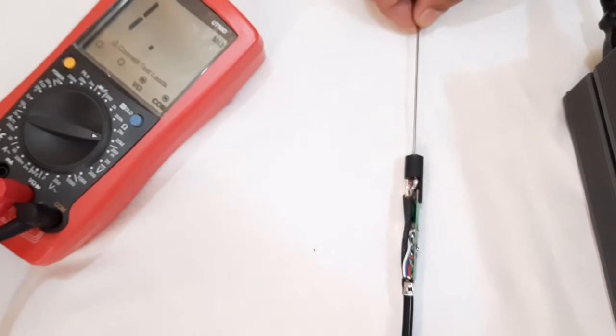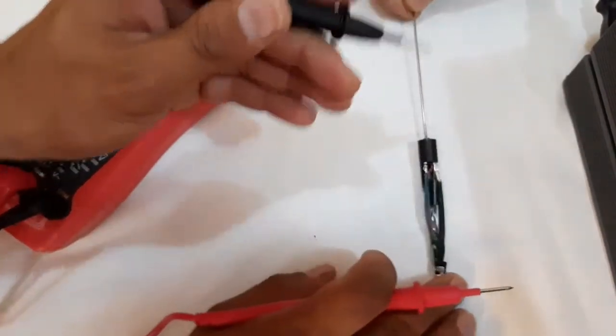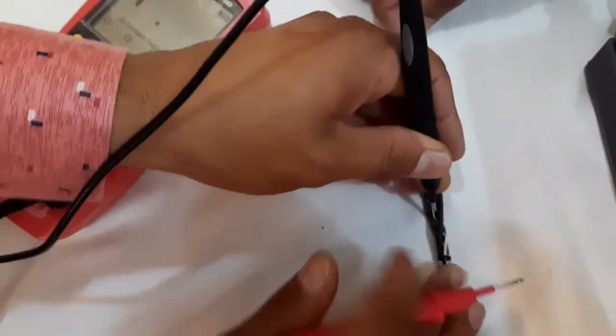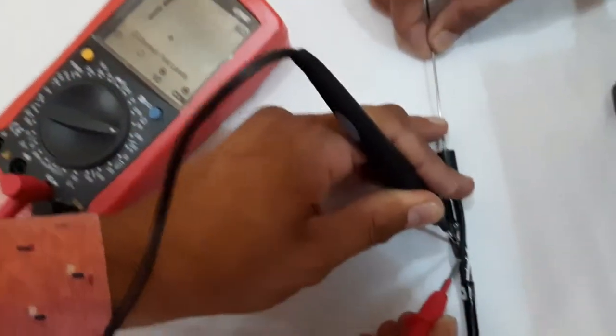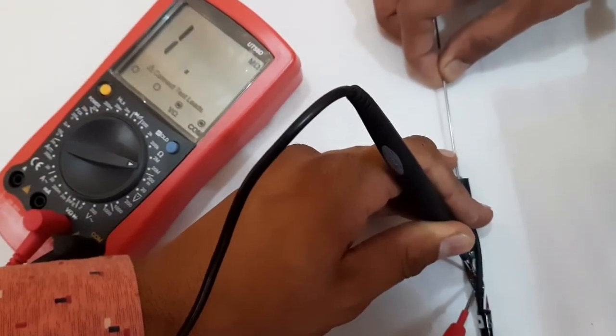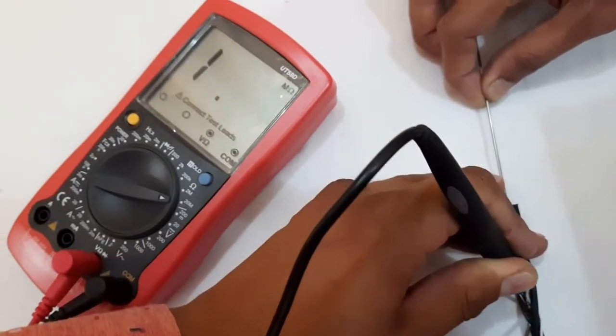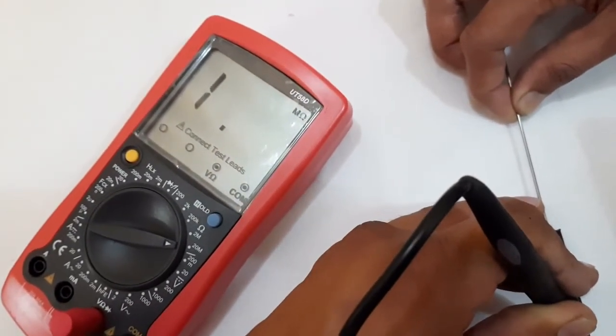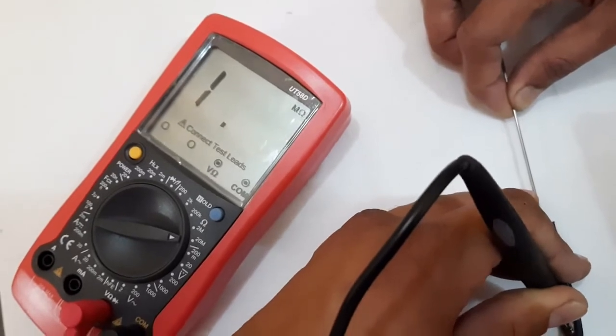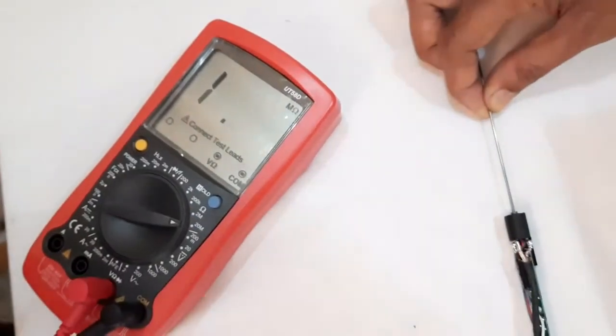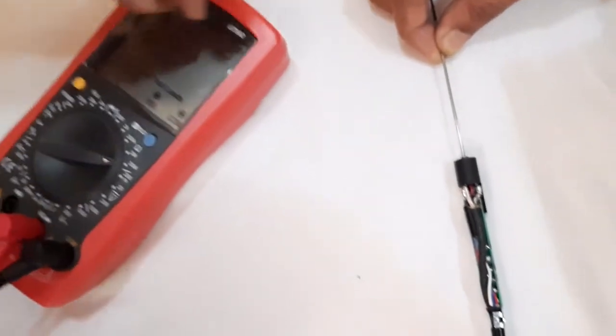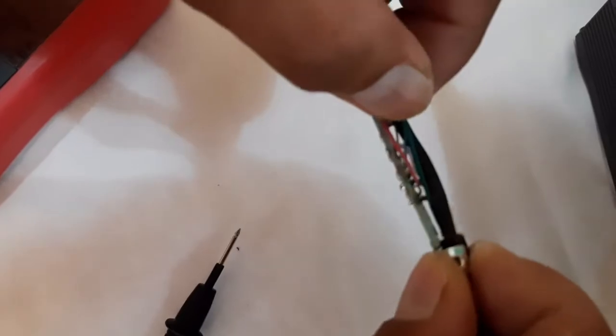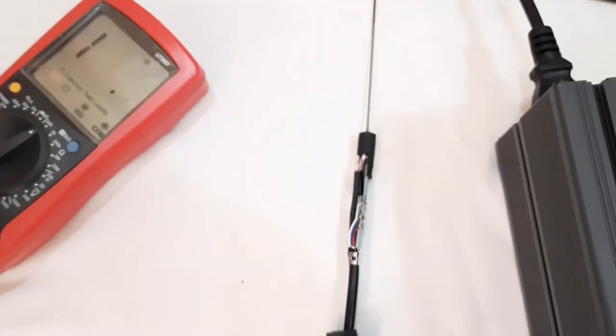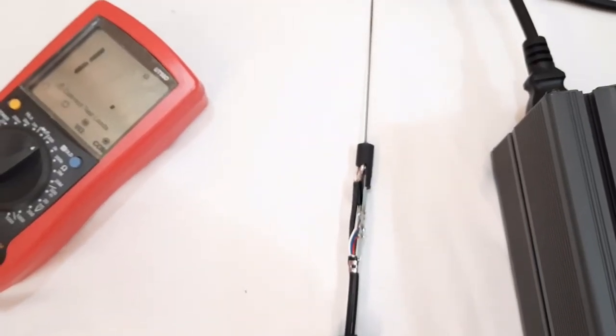So let's measure the resistance between these two wires, the blue one and the red one, with the help of a multimeter. The resistance value is more than 20 mega ohm and close to infinity, so it means the sensor is faulty. We need to just desolder these two wires and take out this faulty sensor and replace it with a good one. Now we have replaced the faulty sensor with a good one.